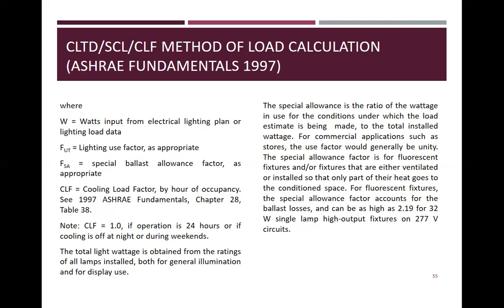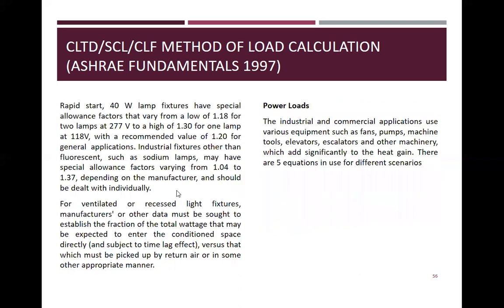For fluorescent fixtures, the special allowance factor accounts for the ballast losses and can be as high as 2.19 for 32 watt single lamp high output fixtures on 277 volt circuit. Rapid start 40 watt lamp fixtures have a special allowance factor that varies from a low of 1.18 for two lamps at 277 volts to a high of 1.3 for one lamp at 118 volts, with a recommended value of 1.2 for general application. Industrial fixtures other than fluorescent, such as sodium lamps, may have a special allowance factor varying from 1.04 to 1.37, depending on the manufacturer, and should be dealt with accordingly.